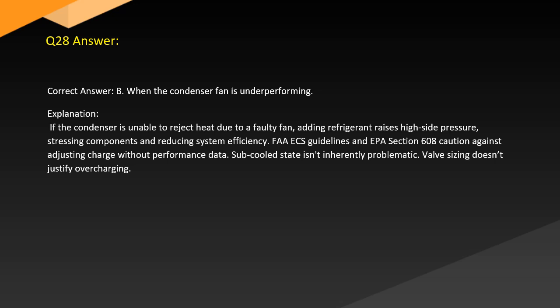Answer. Correct answer: B. When the condenser fan is underperforming. Explanation: If the condenser is unable to reject heat due to a faulty fan, adding refrigerant raises high side pressure, stressing components and reducing system efficiency. HVAC guidelines and EPA Section 608 caution against adjusting charge without performance data. Subcooled state isn't inherently problematic. Valve sizing doesn't justify overcharging.